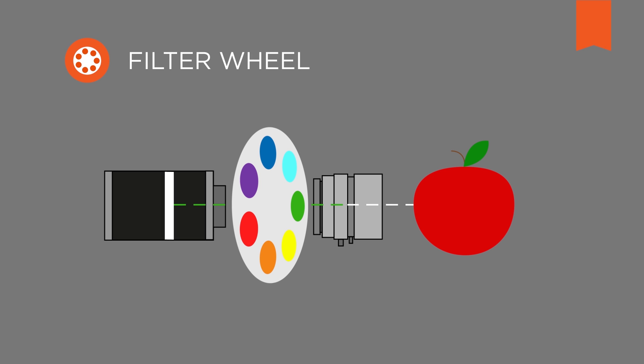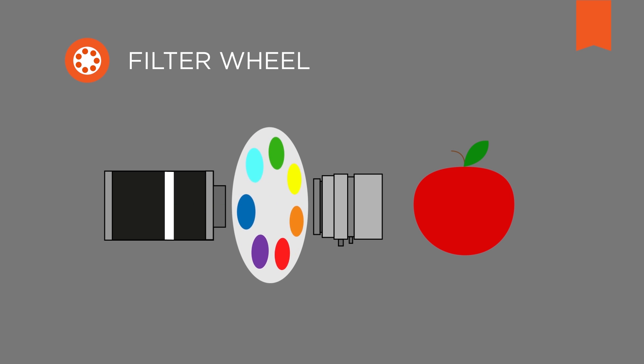Objects captured by filter wheel cameras are scanned sequentially, because the camera captures single wavelengths. For additional wavelengths, the filter wheel must be moved to the desired filter. This results in a reduced scanning speed, and therefore it is not usable on moving targets.